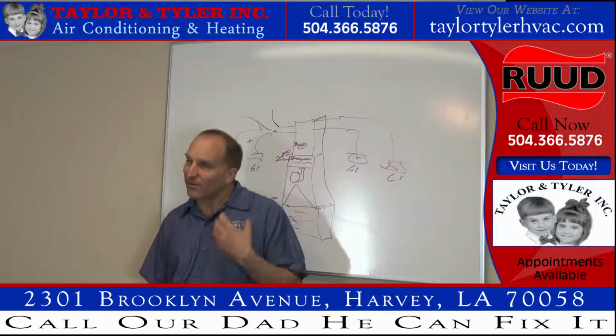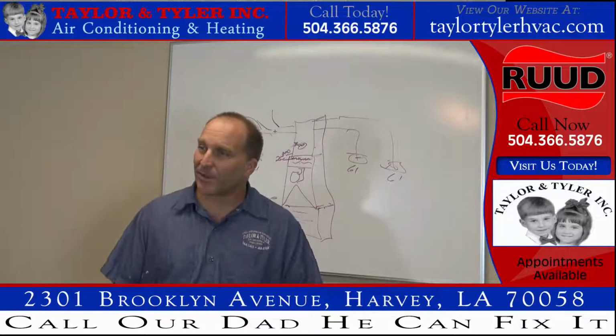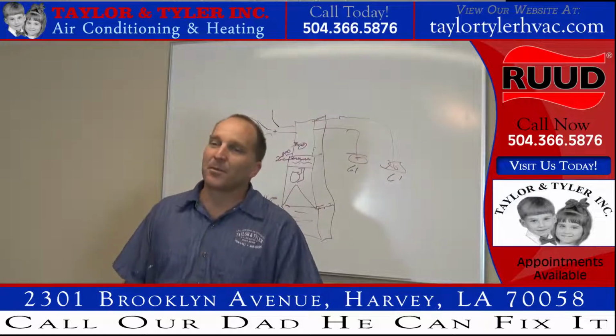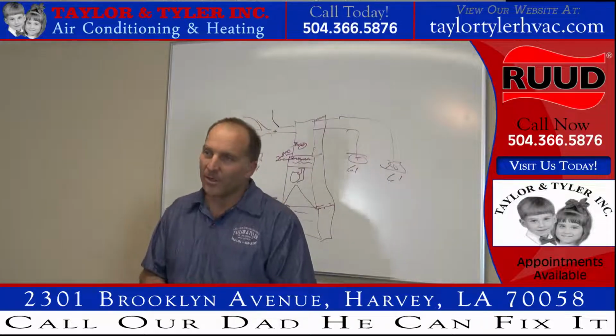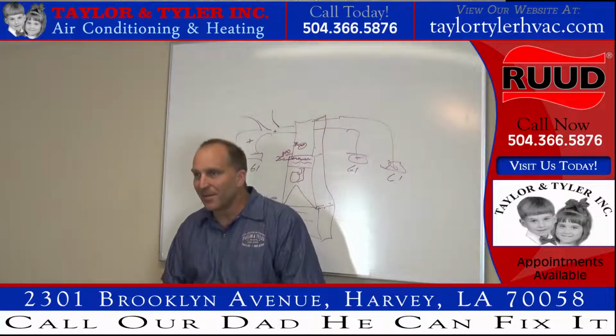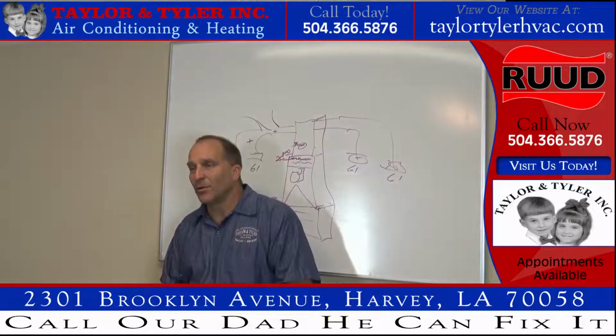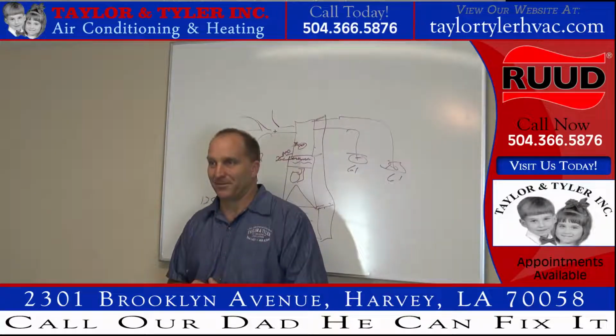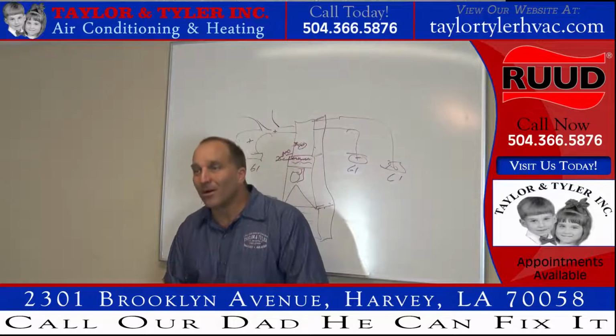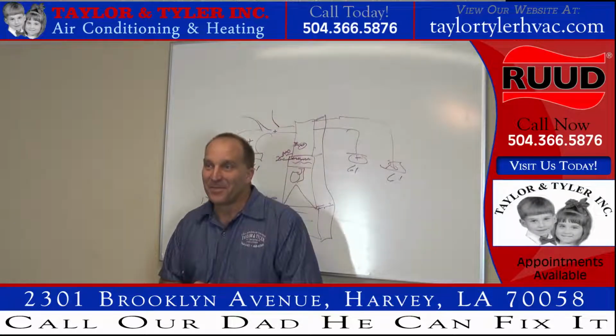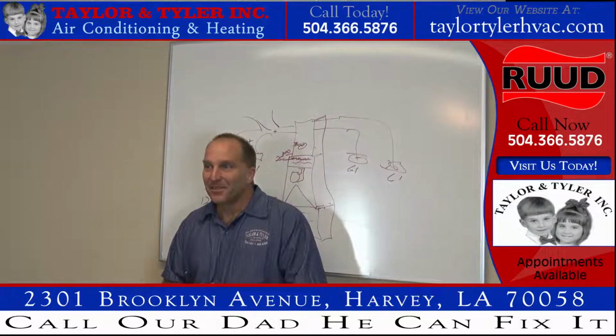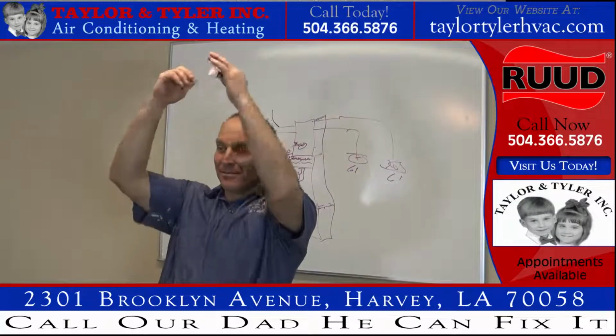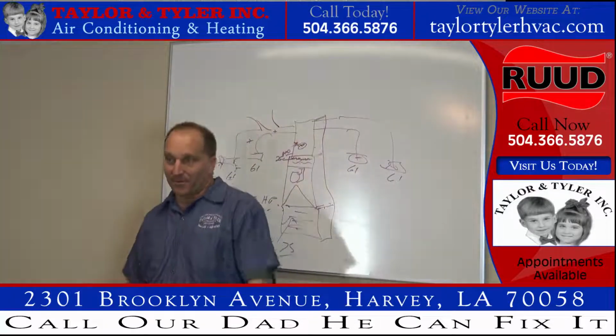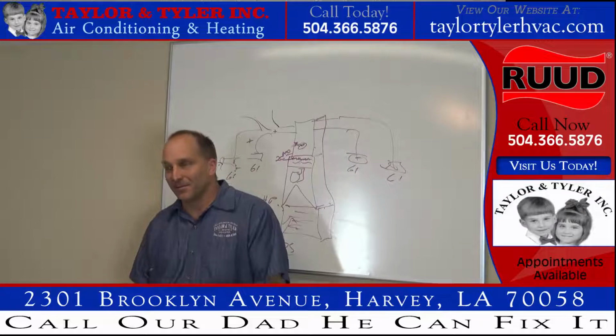I'm assuming you have a 3-ton coil because you told me you had a 3-ton condenser, right? Did you look at it? Did you lower the blower speed? No. You got the wrong coil. Okay. So I got 3 tons of air running over a 2-ton coil. Okay, it ain't gonna work.